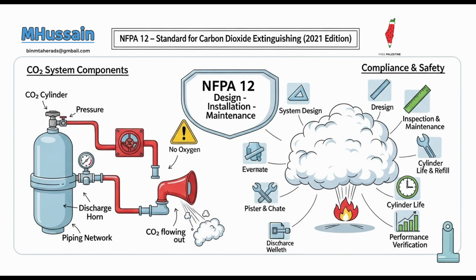Pressure tests of the piping must be performed using a dry, non-corrosive gas like nitrogen or CO2, increasing pressure in 50 psi increments. For high-pressure systems with stop valves, piping from the supply to the stop valves must withstand a minimum of 1,000 psi, 6,895 kPa, with less than a 10% pressure drop over 2 minutes. Strict pressure testing. And piping between stop valves and nozzles must withstand 600 psi, 4,137 kPa, with similar leakage limits. For low-pressure systems, normally pressurized piping is tested at 300 psi, 2068 kPa, with no leakage permitted.